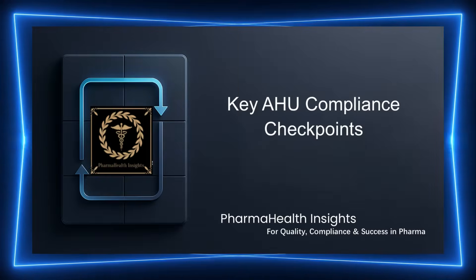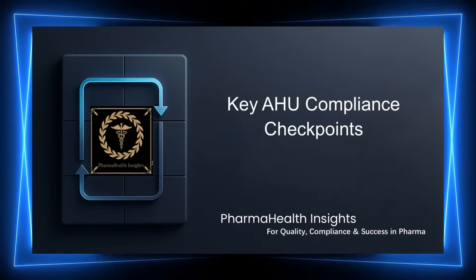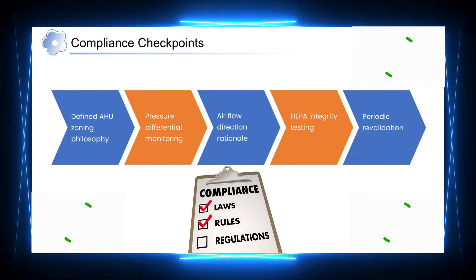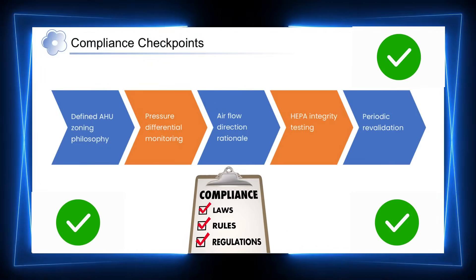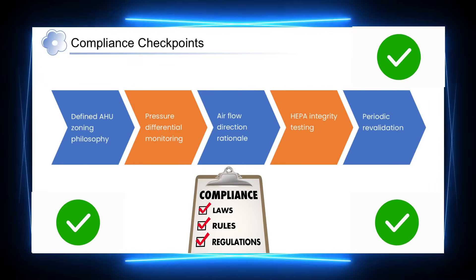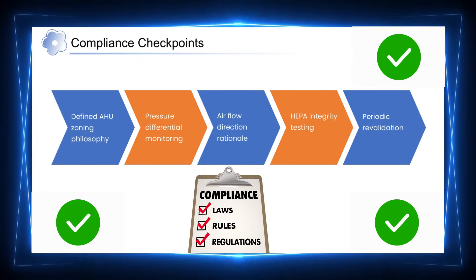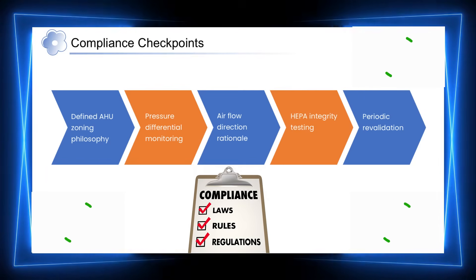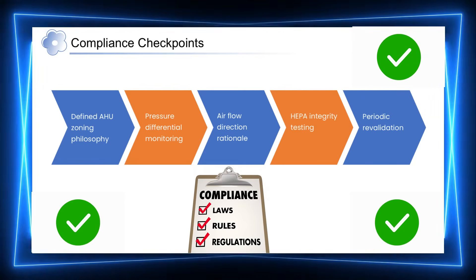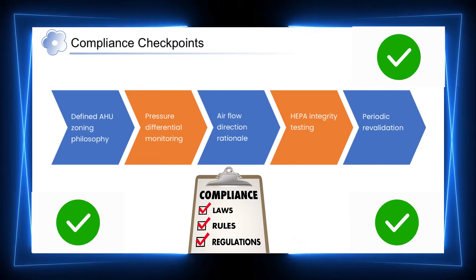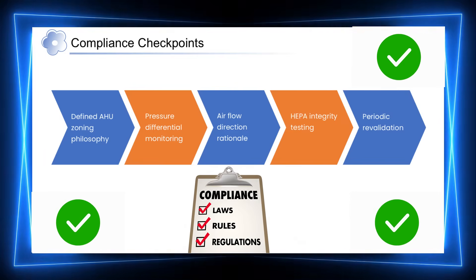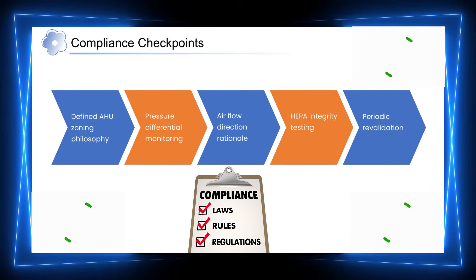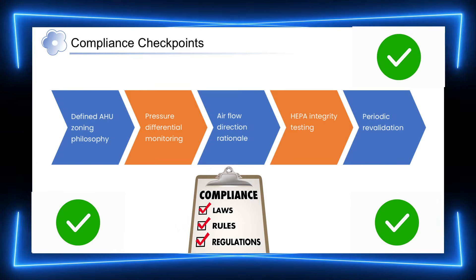And these expectations translate into specific checkpoints. Auditors typically focus on a clearly defined AHU zoning philosophy that supports segregation and contamination control. Pressure differentials must be continuously monitored, and airflow direction should be clearly understood and justified. In addition, HEPA filters must be periodically integrity tested, and the overall AHU performance should be reviewed through revalidation at defined intervals. These checkpoints together demonstrate that the AHU is operating in a controlled and compliant manner.